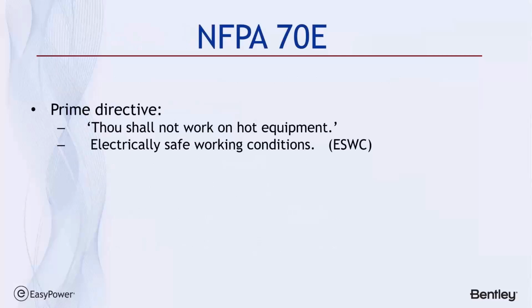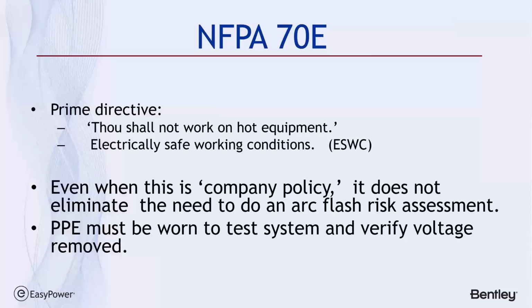Now, these are my own words, but the prime directive of NFPA 70E is thou shalt not work on hot equipment. And as soon as a corporation or company decides that's going to be our policy, then that means our employees know how to put the equipment in an electrically safe working condition. That is referred to as ESWC, and it's defined in NFPA 70E. Even when it's company policy that you will not have electrical hot work, it doesn't eliminate the need for an arc flash assessment. And if you ask why, it's because PPE must be worn to test the equipment.